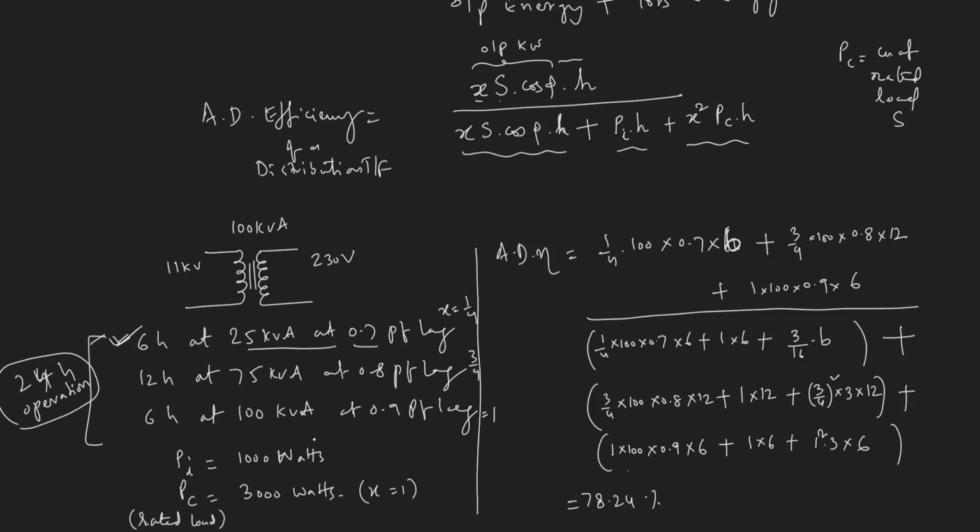Under such operation, one should be very careful about the core losses. Core losses exist at all times, right? That is why, while designing distribution transformers, they check what percentage of core loss is happening in the transformer, and they try to minimize it as much as possible without compromising other parameters. So a distribution transformer gets a bit of extra focus.